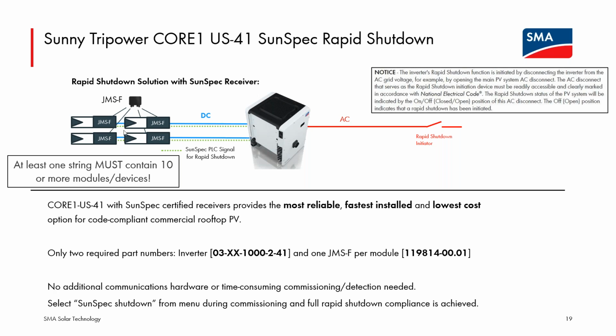Very quickly, the receiver elements at the array will see that the signal has gone away and begin isolating their modules from the string they are part of, taking the array into shutdown and meeting all of the voltage requirements of rapid shutdown. So, aiming for a very, very simple way to trigger this, any AC disconnect upstream of the terminals of the inverter, as long as it's adequately labeled, can act as the rapid shutdown initiator.